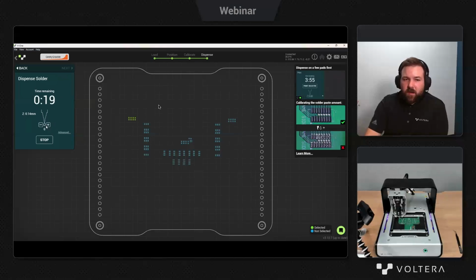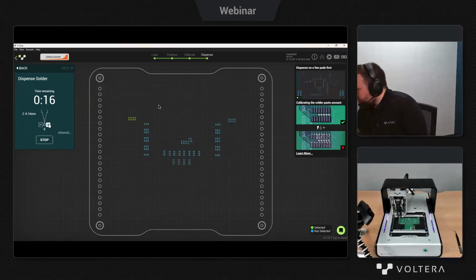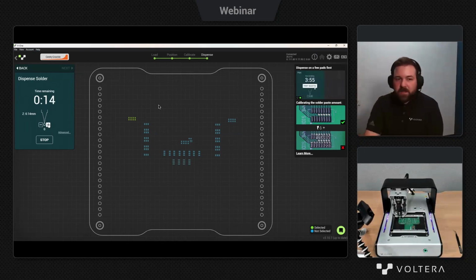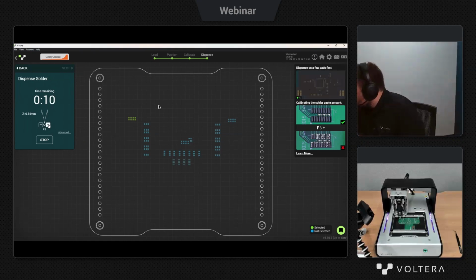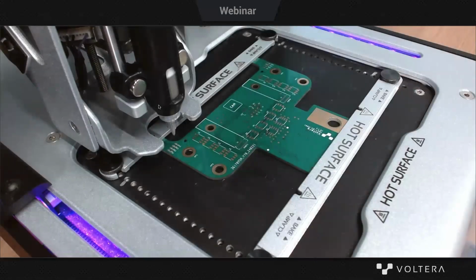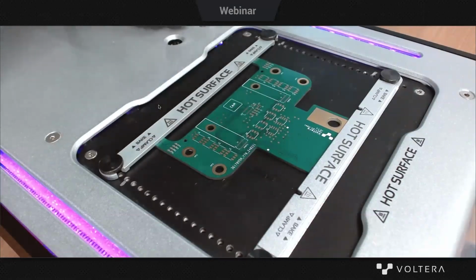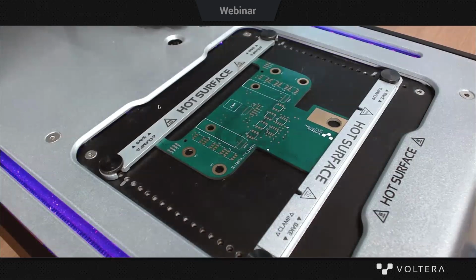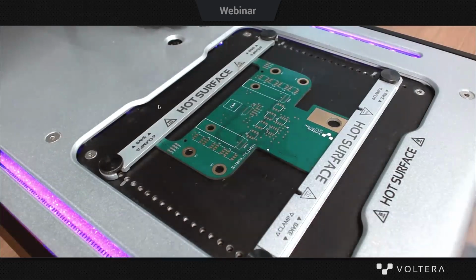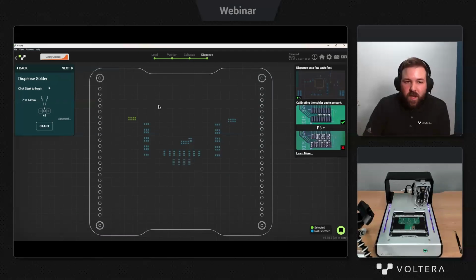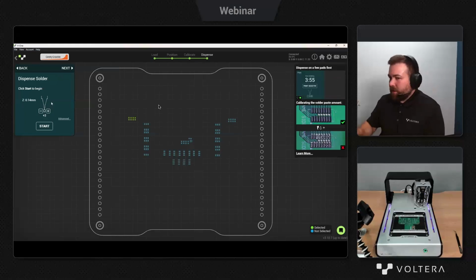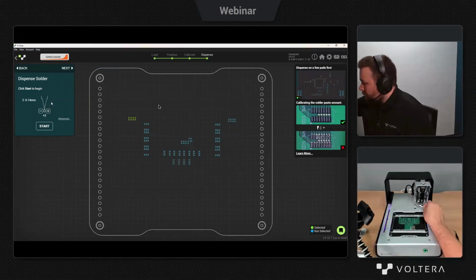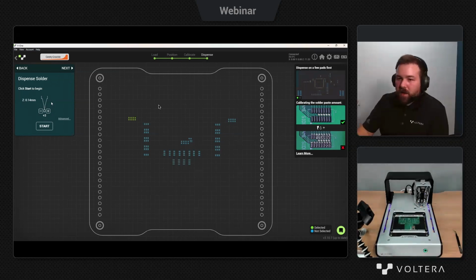So in the software, at this point, I can keep an eye on things and see, do I need more flow? Do I need less flow? And I can click plus or minus to set that position of the actuator inside the cartridge to start with. So I'll just take a quick view of my couple of pads here. It looks like the first couple were a little bit on the light side, and then in the software you noticed I added 2. So I might just add 1 more here just to get a little bit more flow coming out. And I can just wipe those couple of pads clean with a Q-tip. And then we can go and do those same pads again.